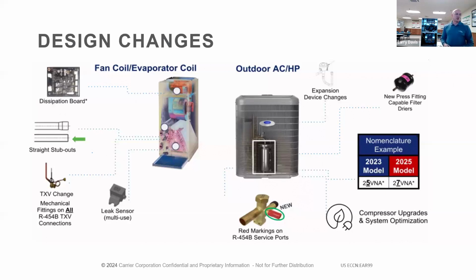So the question is, do we have to change R22 line sets no matter what? You don't necessarily have to. If the line size is correct, you should be fine reusing that line set, but you're going to have to really flush that system out before you put in the new product, because what we don't want is any mix of that old mineral oil or that old R22 refrigerant in this new 454B system. So if it's a running R22 system and you're changing it out to the new 454B, you've really got to make sure that line set's clean. You're going to have to flush it.